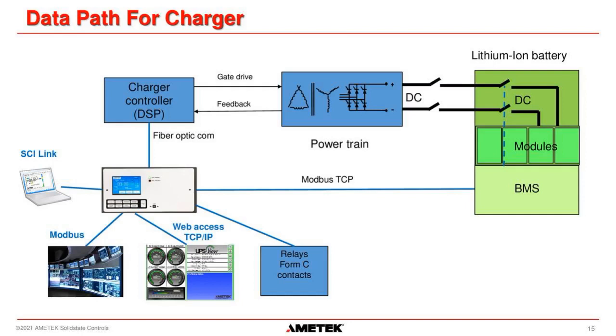The UPS HMI is also capable of communicating with other outside sources. We have an application called SCI Link that connects via USB to the UPS, where you can download data logs and maybe change some alarm set points. We also have Modbus RTU and Modbus TCP available for connecting the UPS to the SCADA system for a particular client. The Modbus also forwards the data collected from the battery through our UPS to the SCADA system. There's also a web app or a website that you can visit on the HMI. And then finally, we have some Form C relay contacts that can be configured for certain alarms.